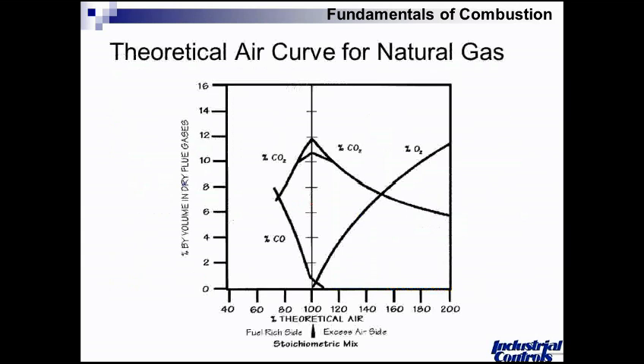This next slide is worth spending a fair amount of time on — it's pretty close to being the single most important takeaway. It captures a lot of what we're going to discuss. If you think about that equation from the previous slide, this is a way to put it into a pictorial format. This curve will change based on fuel type, but in general it will have a very similar shape for many fuels. On the x-axis, 100 represents stoichiometric — the vertical line in the center. It's neither fuel-rich nor fuel-lean; it's just right — the proportions required for perfect combustion in a laboratory.